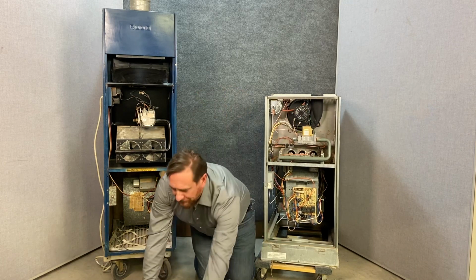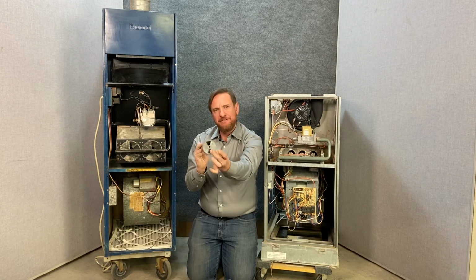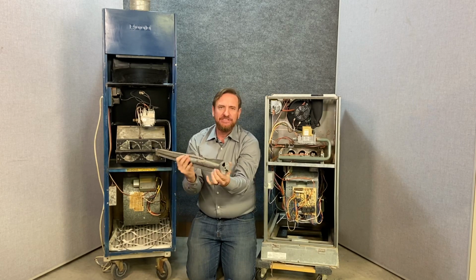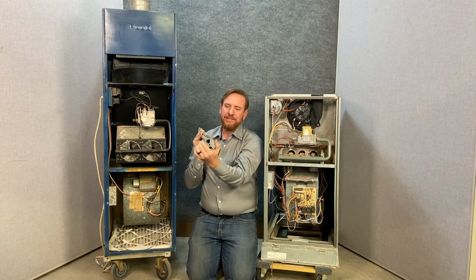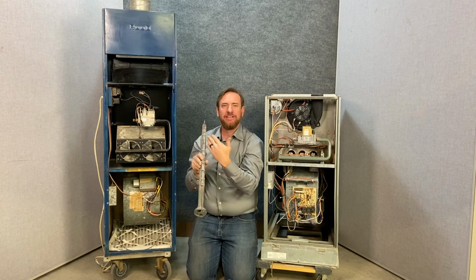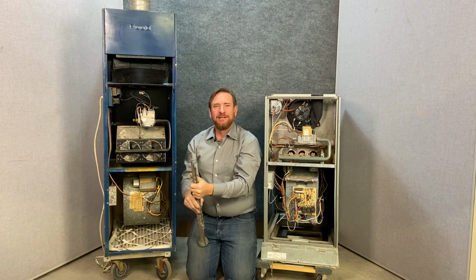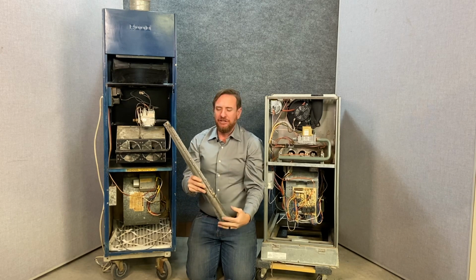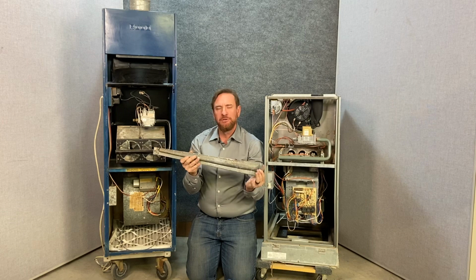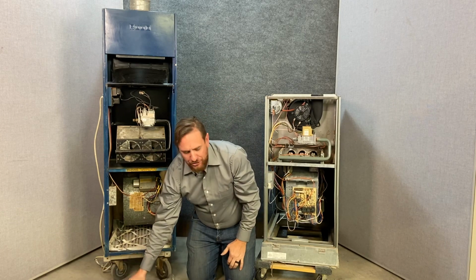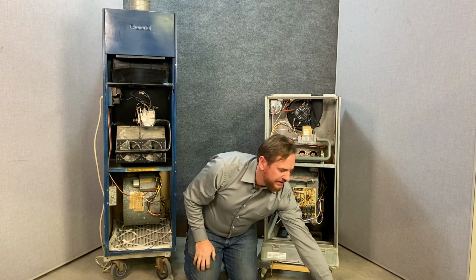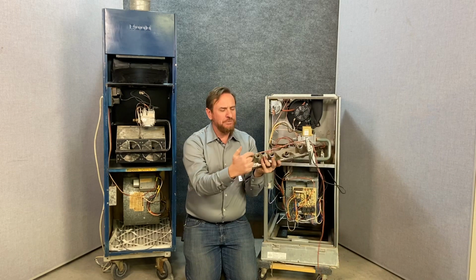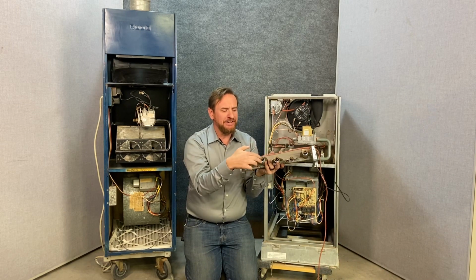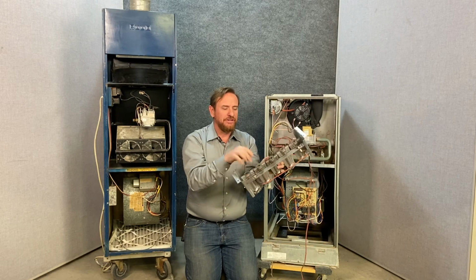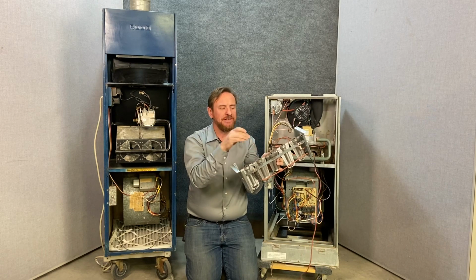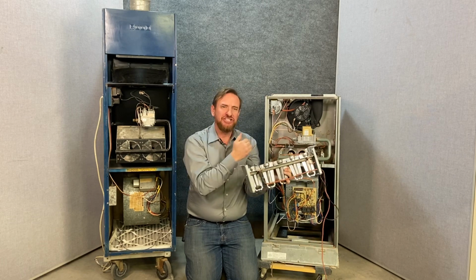And in these older systems, our burners had an air-fuel adjustment. So we had to actually adjust, open and close this opening, so that we could adjust how much air is coming in to set the flame. You're supposed to use a combustion analyzer, but a lot of people just do it by looks, but we had to adjust the air-fuel mixture so this would burn correctly inside that furnace. The new ones are quite simple. The new ones use these inshot burners, and as we shoot the gas in, it mixes with primary air on the sides. These burners are much smaller, mix the air and the fuel, and direct the flame, but it's a nice small one, and it's shooting the flame actually sideways.